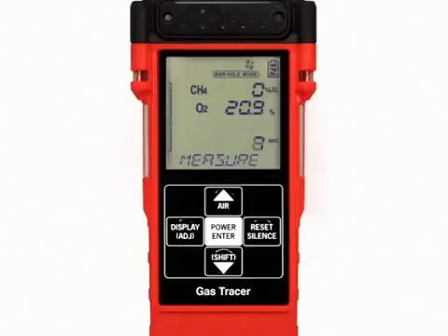If you wish to cancel the measurement, press and release the Reset Silence button. After 15 seconds of sampling, if the combustible gas reading is less than 5% volume, the combustible gas channel will automatically begin displaying in percent LEL. At the end of the sample period, the pump will shut off and the buzzer will sound. Then the peak methane reading and the minimum oxygen reading for the sample period will be displayed. The peak methane reading will also be visually displayed on the graph along the left side of the screen.